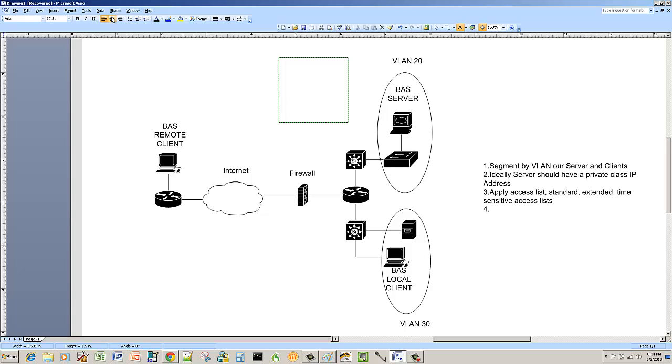Let's do this again. Port 80 is HTTP. Port 443 is HTTPS. Port 25, SMTP. Those are some of the more basic ones that you have open. Now, when you start talking BACnet, when you start talking Modbus, BACnet 47808, if I remember correctly, is the typical BACnet port. Then you've got Modbus, you've got LAN, all sorts of different things, and you can have ports open.